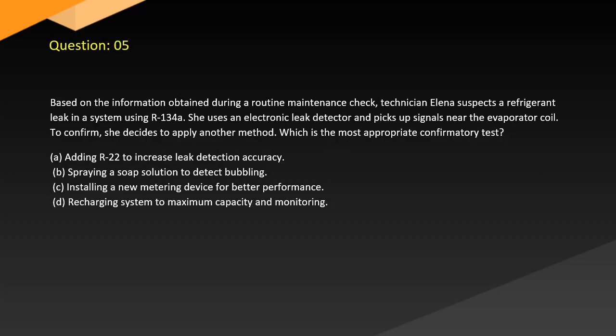Question 5. Based on the information obtained during a routine maintenance check, technician Alina suspects a refrigerant leak in a system using R-134a. She uses an electronic leak detector and picks up signals near the evaporator coil. To confirm, she decides to apply another method. Which is the most appropriate confirmatory test? A. Adding R-22 to increase leak detection accuracy. B. Spraying a soap solution to detect bubbling. C. Installing a new metering device for better performance. D. Recharging system to maximum capacity and monitoring.